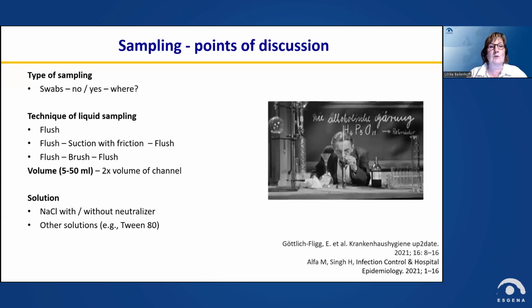It has to be adapted to the volume of the channel. So you really have to have a look at the different endoscope you want to sample. And then you can also use a saline with and without neutralizer. And as I showed you, it also depends if you just sample with neutralizer, or if you add the neutralizer later. There are also other solutions like Tenside, like Tween 80, which you can also add. So there are a lot of variations, and there is also, with the culturing, the discussion of filtration or centrifugation, and the trend is really to filtration.